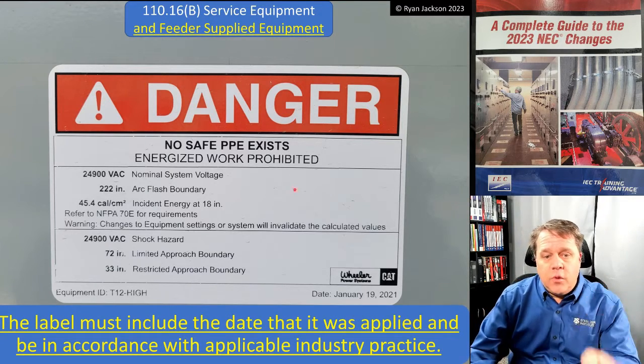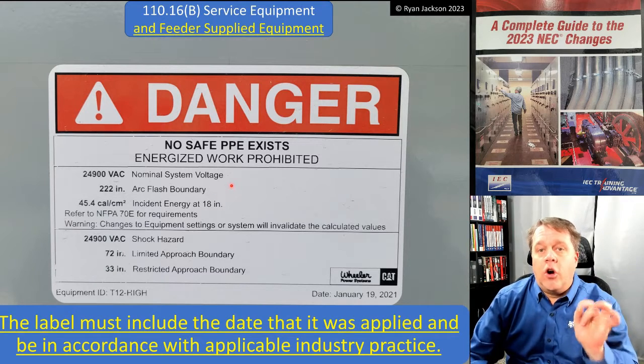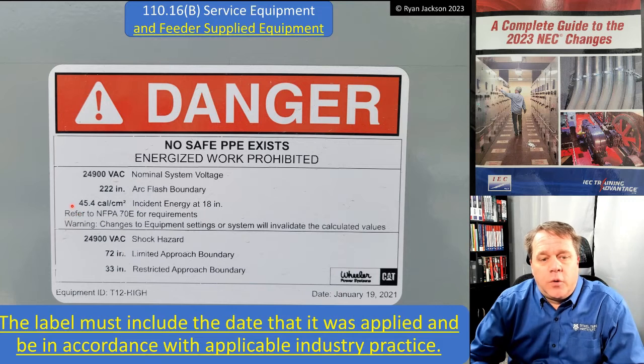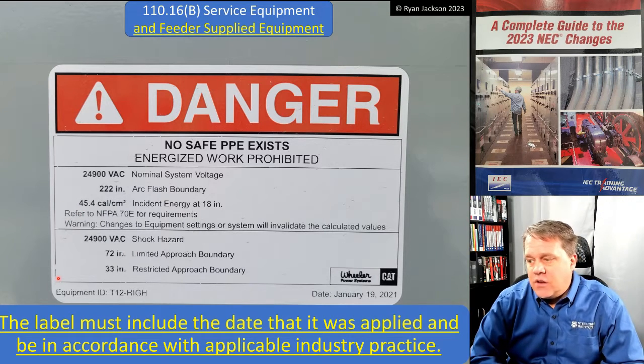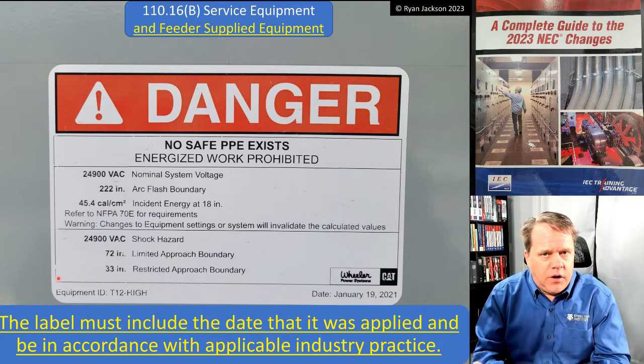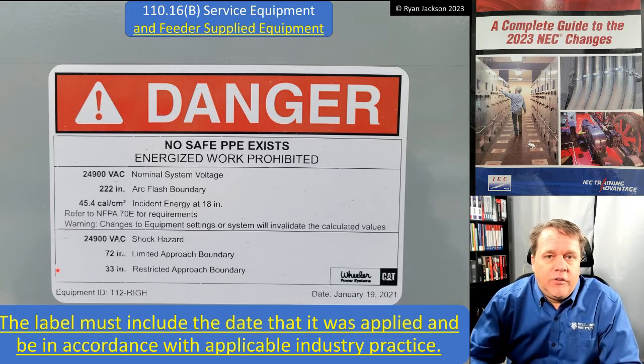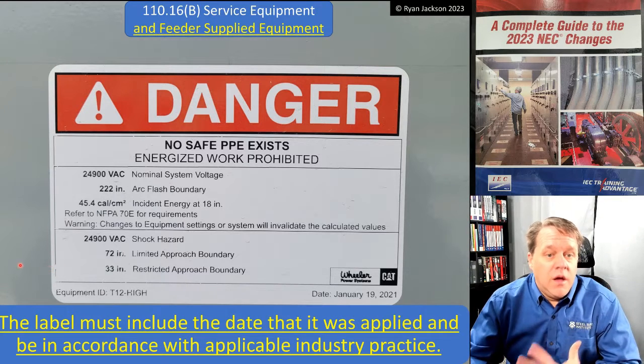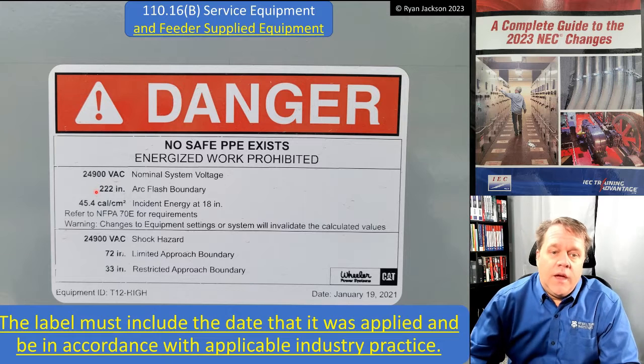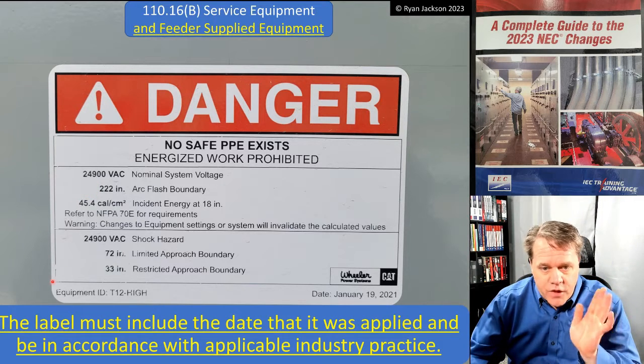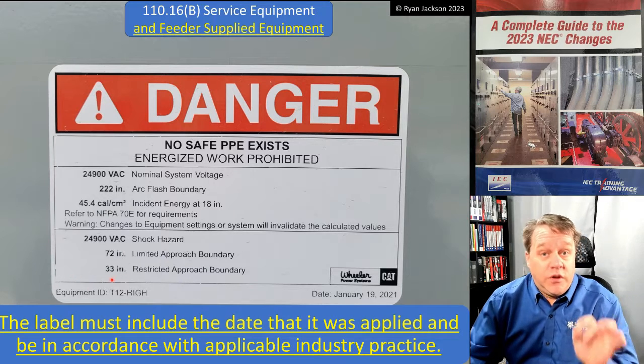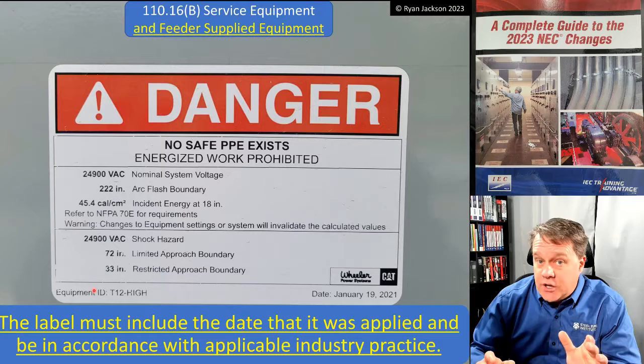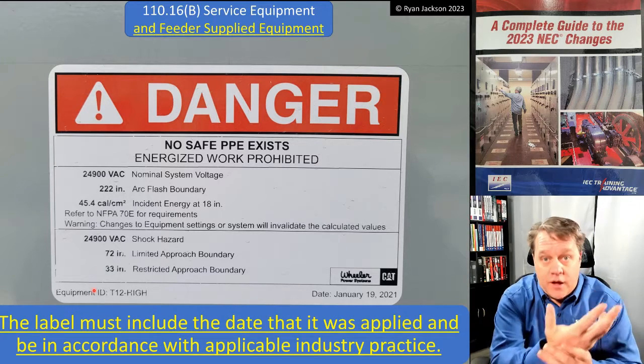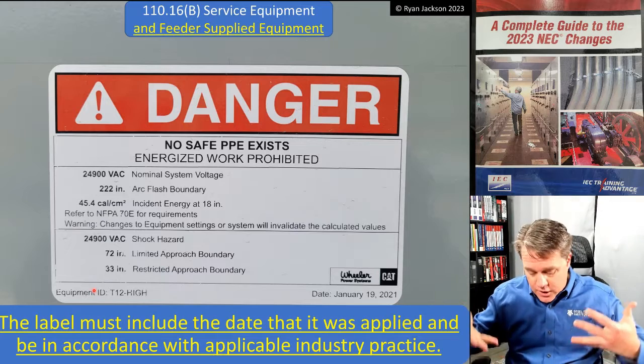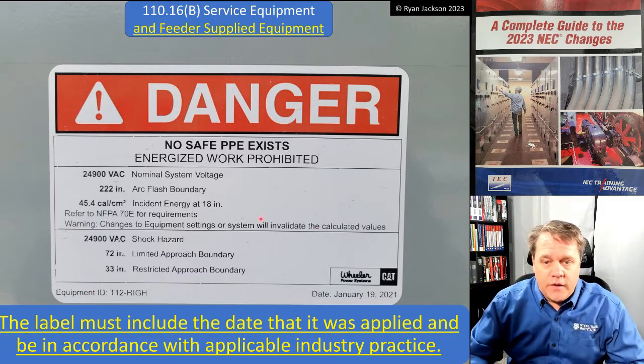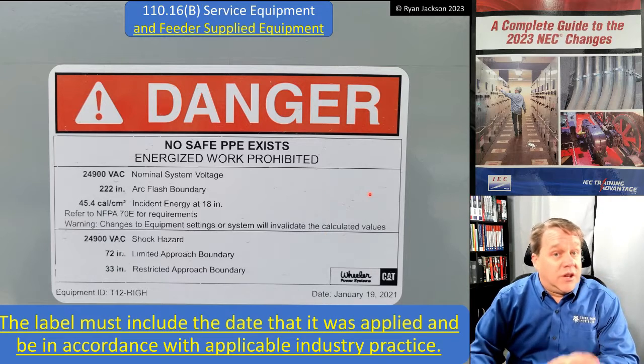Okay? So 222 inches is the arc flash boundary. That's where you get a second degree burn on exposed skin. The incident energy, 45 calories per square centimeter. That's a measurement of how nasty the fireball is, right? It's a measurement of energy. So 45 calories. I better have 45 calorie rated equipment if I'm within 222 inches. And then if I'm within the limited approach boundary, within the restricted approach boundary, that's where I'm going to have shock protection PPE, and that's where I'm going to have my rubber gloves and my leather protectors over them, right? And you're going to have shoes that are rated for EH and everything else that goes along with it. So you got to have a sticker in accordance with applicable industry standards.